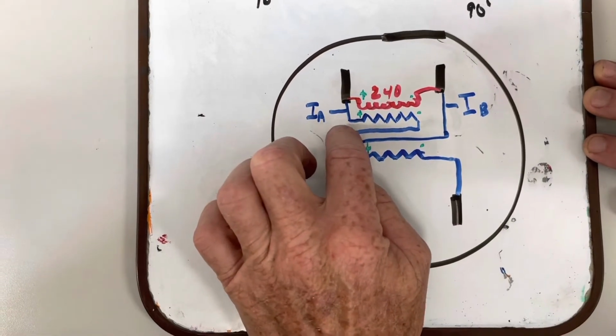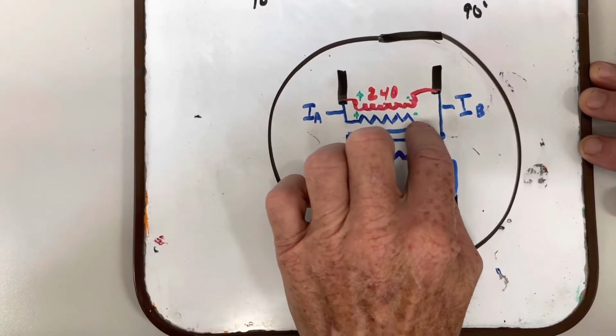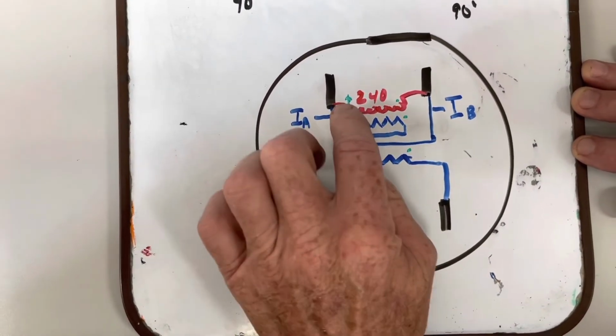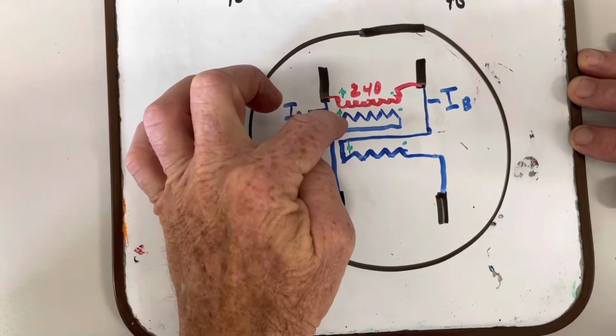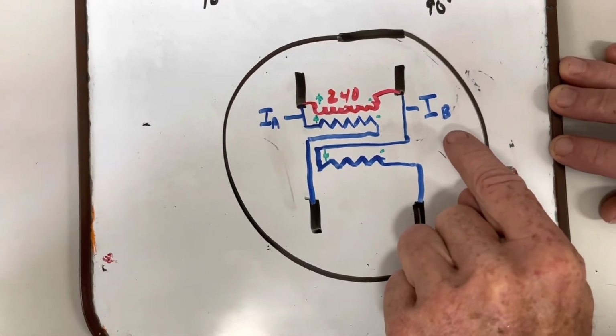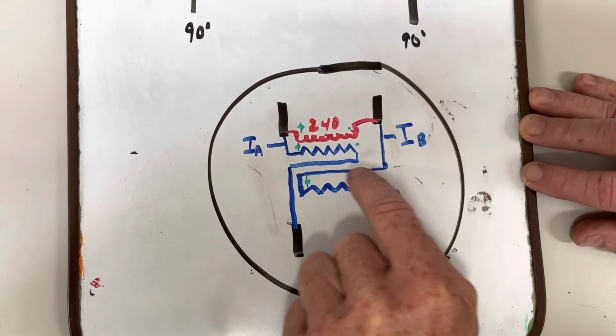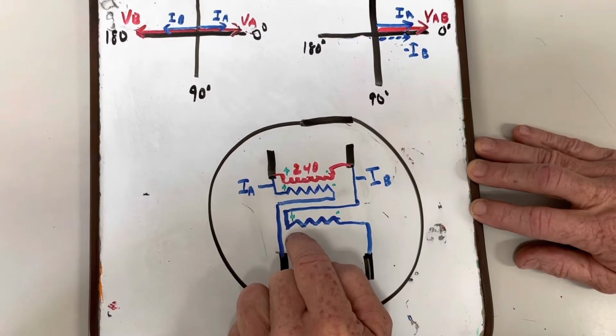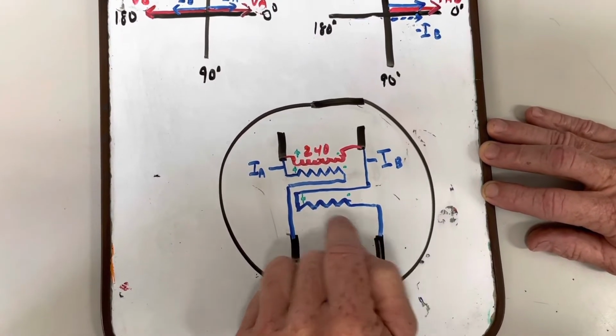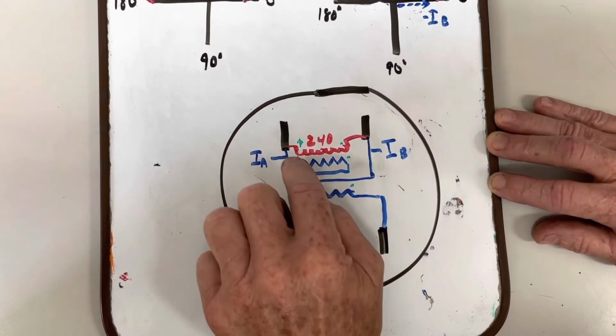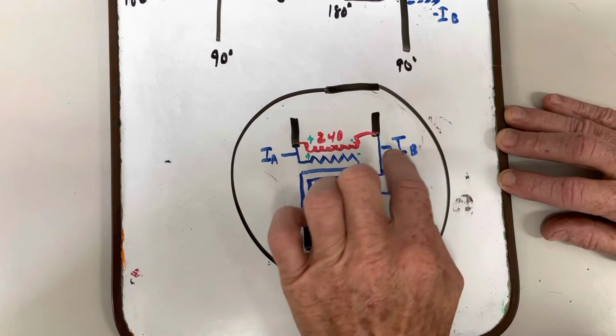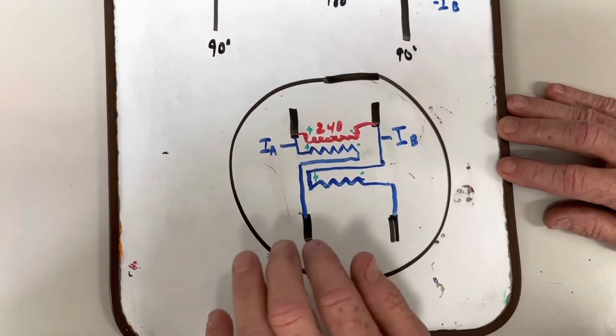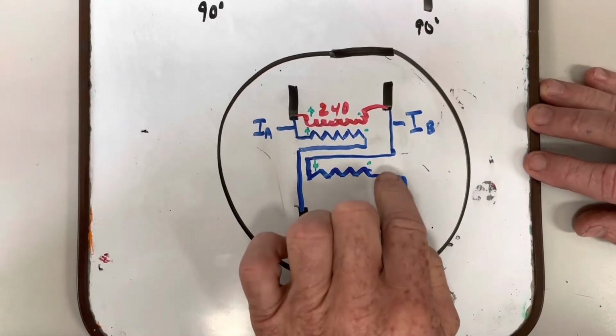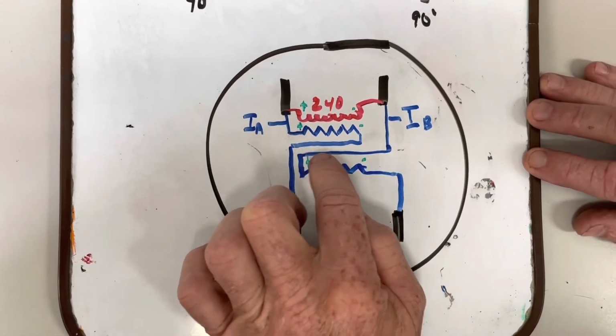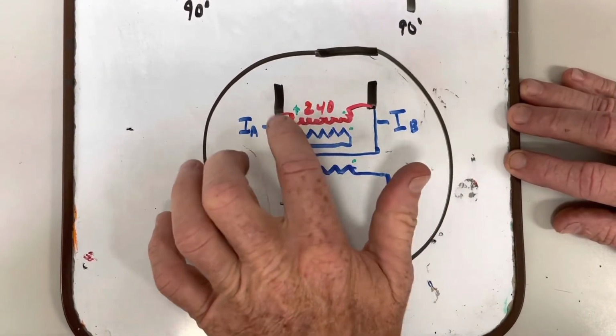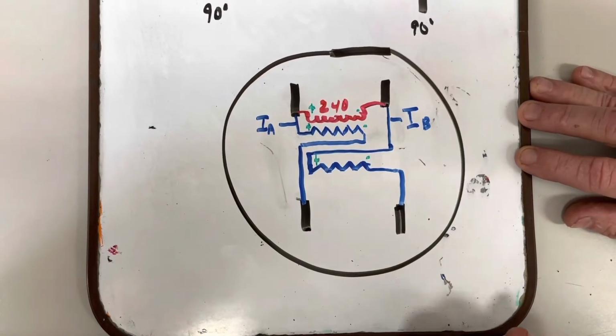So current A, since it's at 0 degrees, the current goes forward across the potential coil and comes out, showing the polarity markers of plus and plus on the current coils. Now current B, we know current B is 180 degrees out. So what we have to do is reverse that current through the coil and come in reverse flow, thus making it a positive and a positive, not a negative and a positive. If these 2 were just both forward through this coil, it would buck and we would have 0 consumption completely. So we have to reverse current B 180 degrees and come through the coil in order to keep all my positives on the same time and meter watt hours correctly.